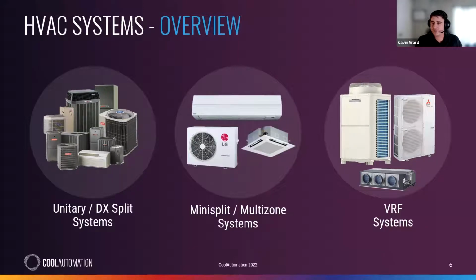They're really not too different, to be honest. Both have that inverter outdoor or the varying capacity capabilities. Really, the main difference is a mini split is typically 1-to-1, or a multi-zone system has a home run pipe and communication wire from the outdoor to the indoor. A VRF system will have multiple outdoor units connected to that single system.